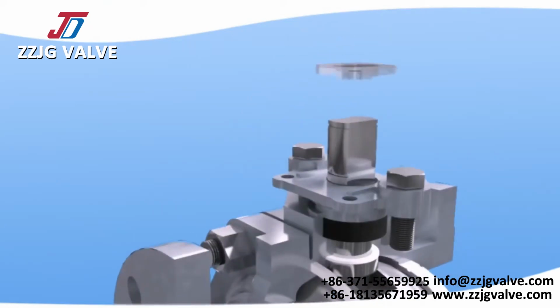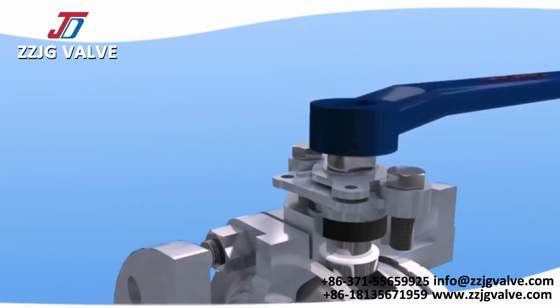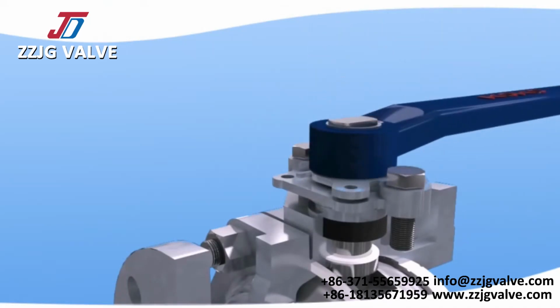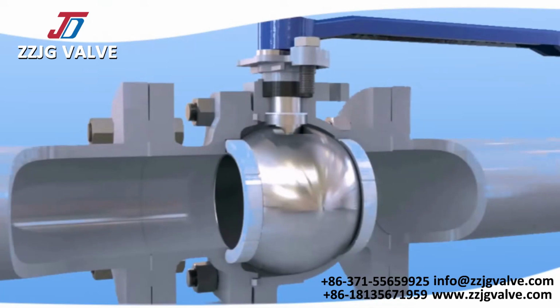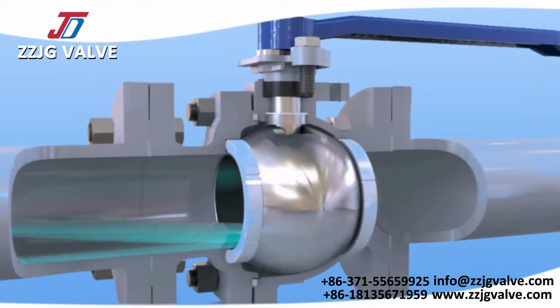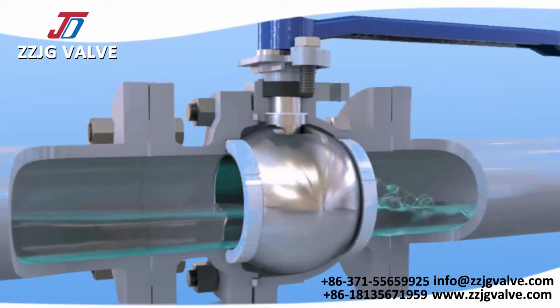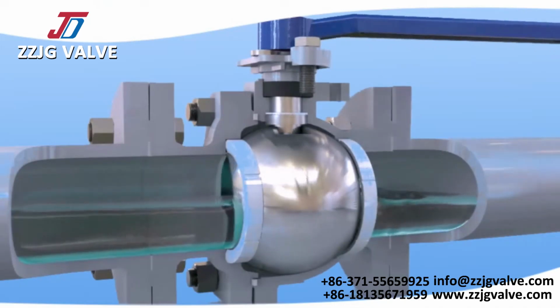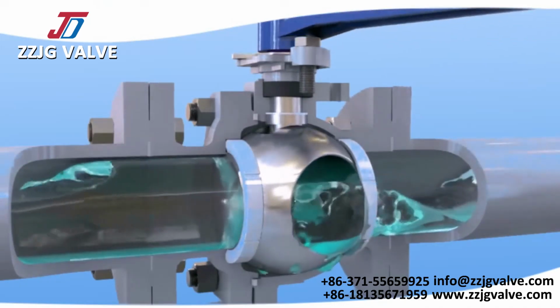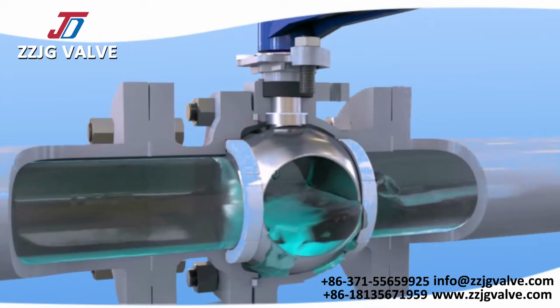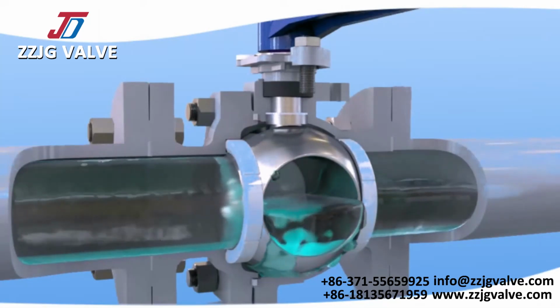2. Small resistance. When the ball valve is open, the section areas of the ball channel, body channel, and the connection pipeline are the same. The medium flowing through the ball valve is equal to flowing through the section of direct piping. The flow resistance of the ball valve is minimum among all kinds of valves.